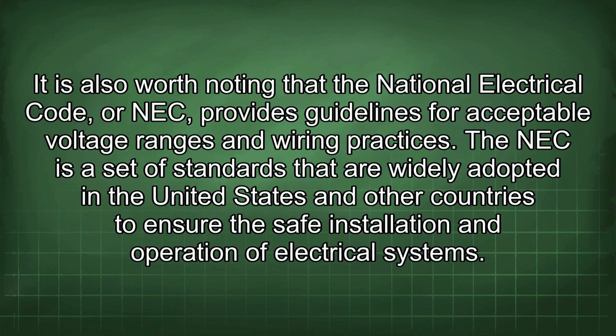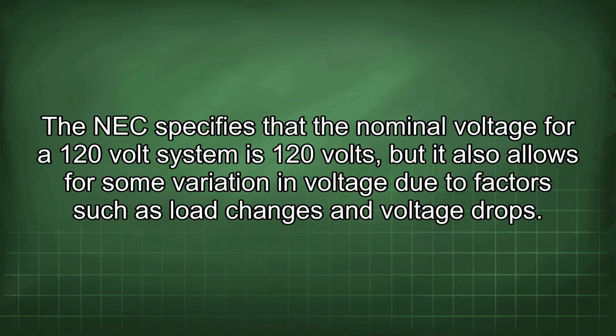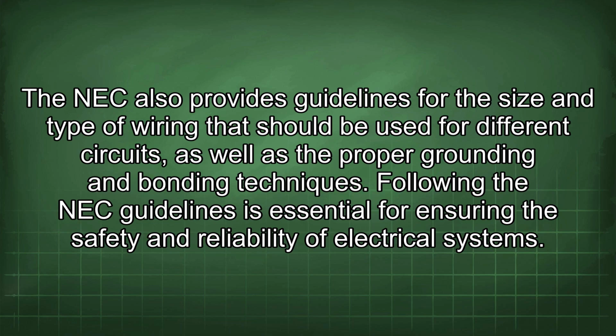It is also worth noting that the National Electrical Code, or NEC, provides guidelines for acceptable voltage ranges and wiring practices. The NEC is a set of standards that are widely adopted in the United States and other countries to ensure the safe installation and operation of electrical systems. The NEC specifies that the nominal voltage for a 120-volt system is 120 volts, but it also allows for some variation in voltage due to factors such as load changes and voltage drops. The NEC also provides guidelines for the size and type of wiring that should be used for different circuits, as well as the proper grounding and bonding techniques. Following the NEC guidelines is essential for ensuring the safety and reliability of electrical systems.